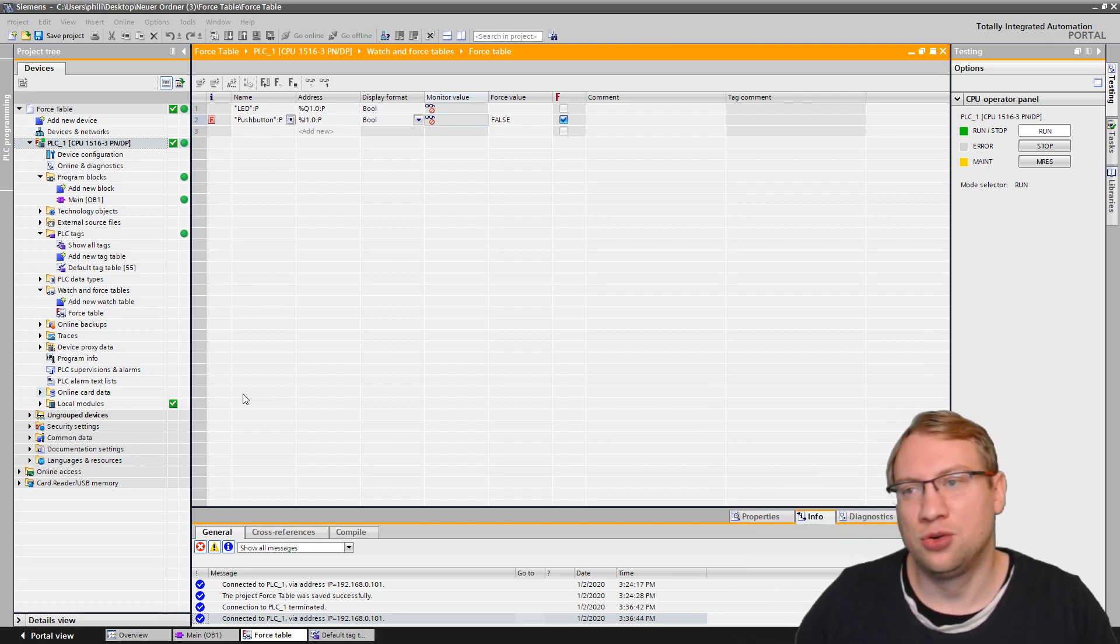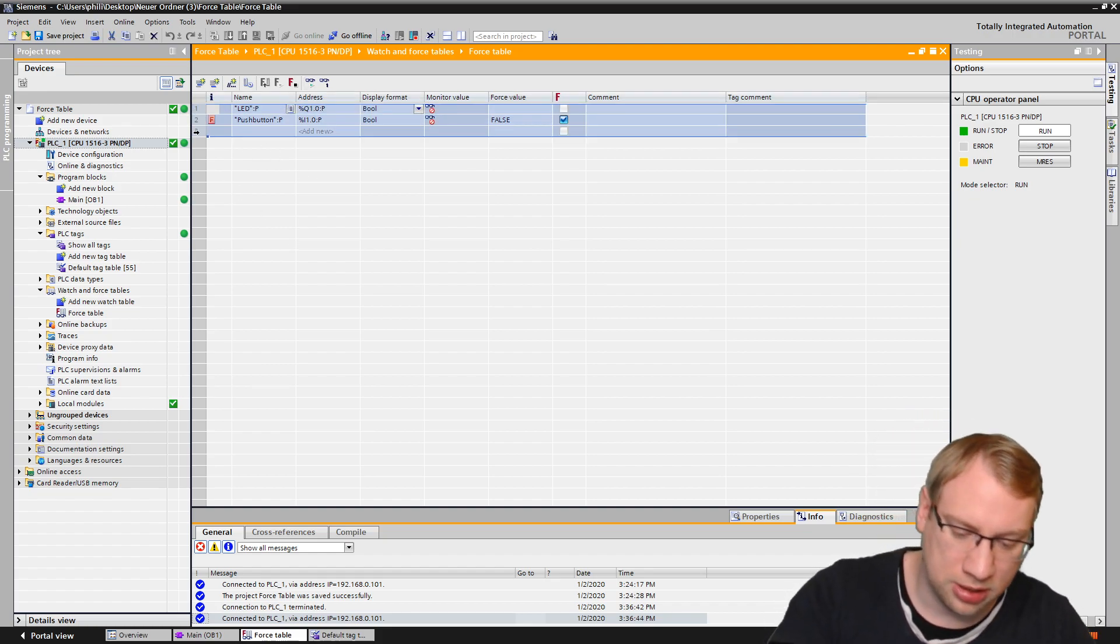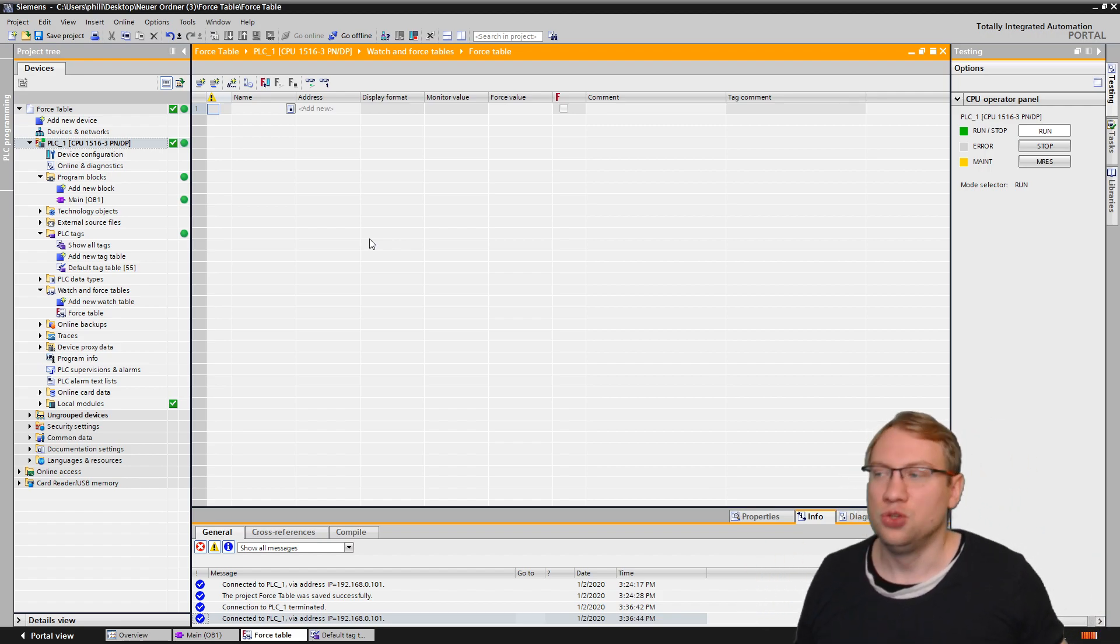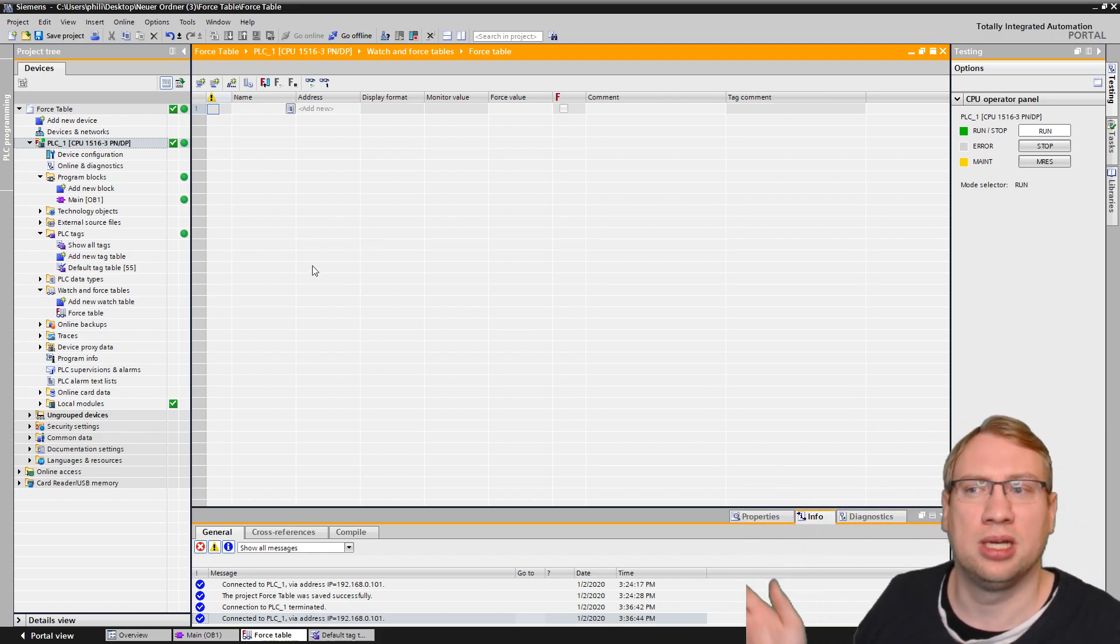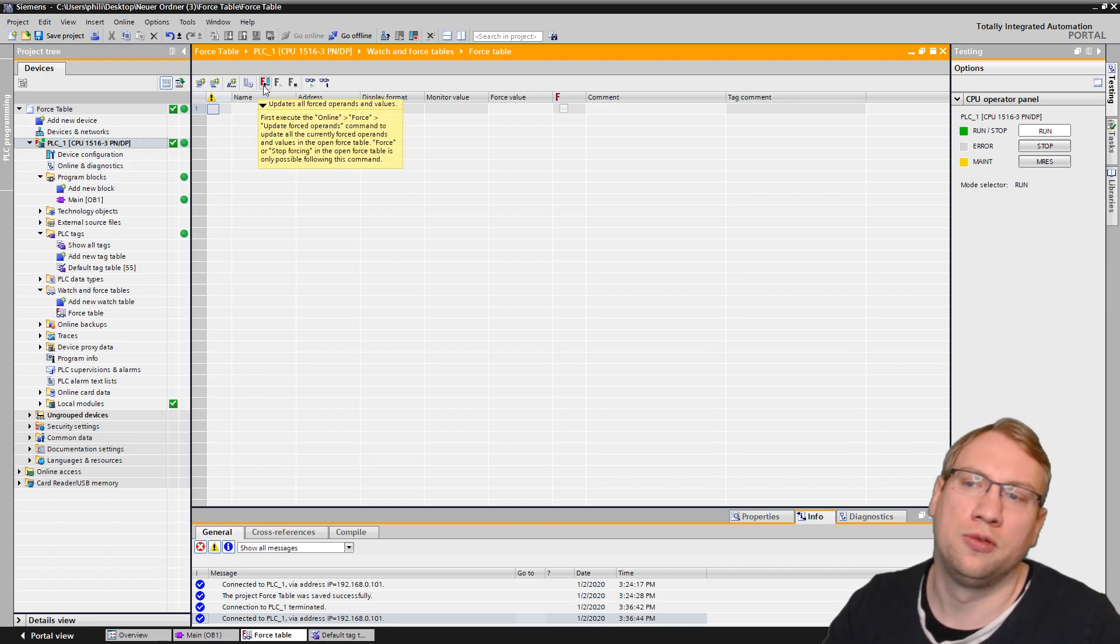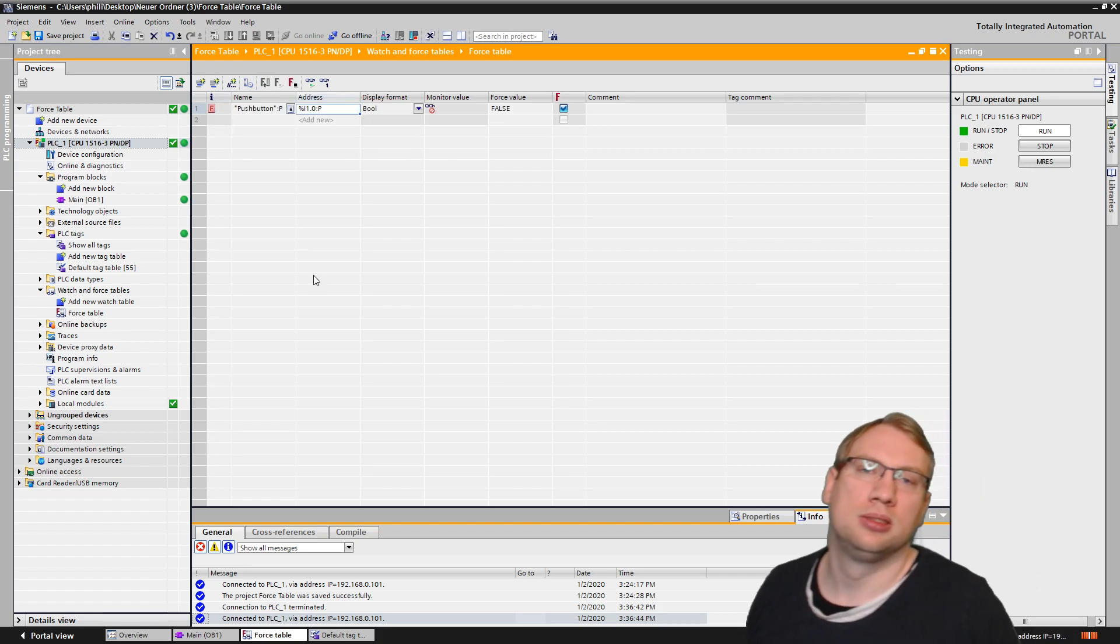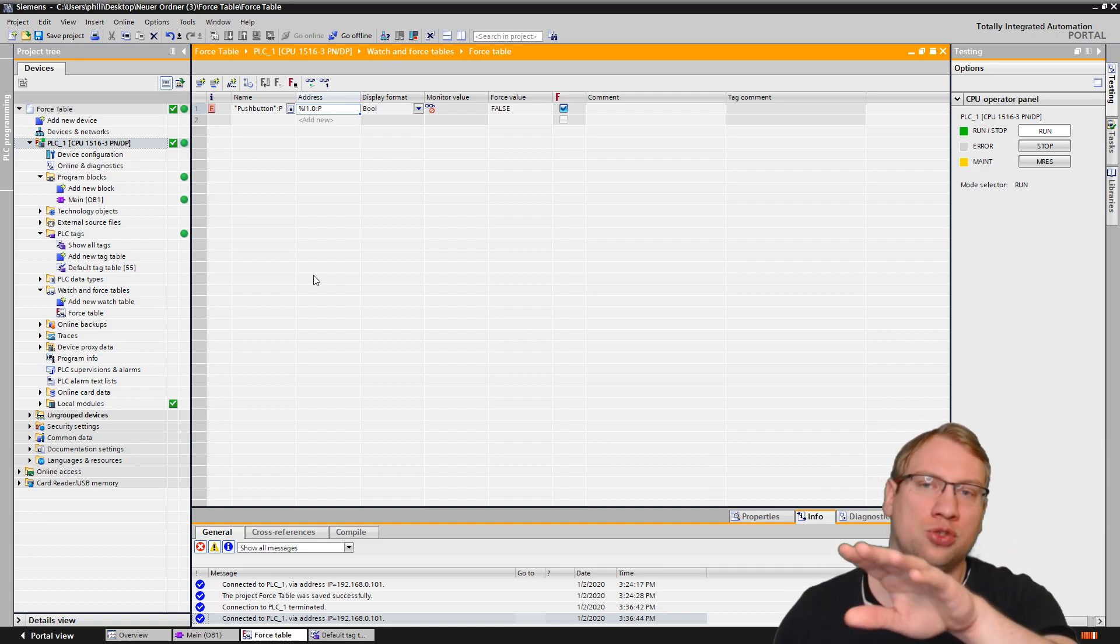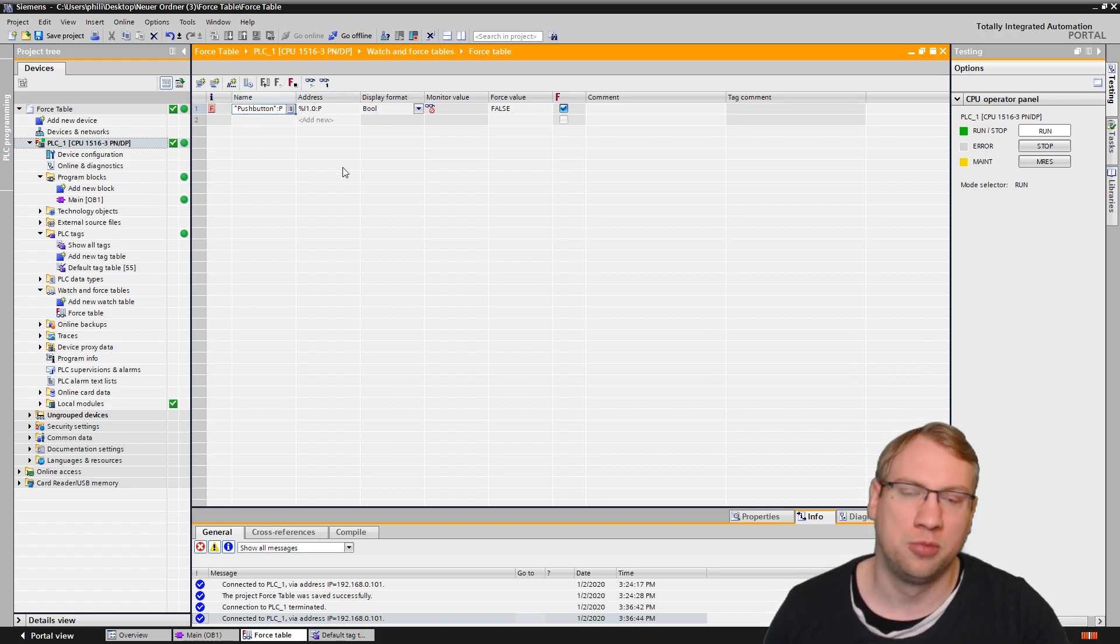Then it could be that you were not the one that made this force table. Someone forced the variables, and you don't actually see what they did. You know, hey, maintenance LED is on, force is active. You go online, force is active, but you do not have the variables here. That's why TIA portal has this button. When you're online, it says update all forced operands and values. If I click on this, TIA portal will grab everything that is right now being forced inside the PLC and put it into your list. So I can now see, hey, ah, okay, someone forces this push button.